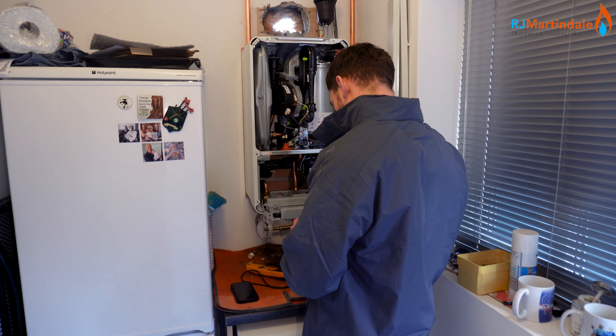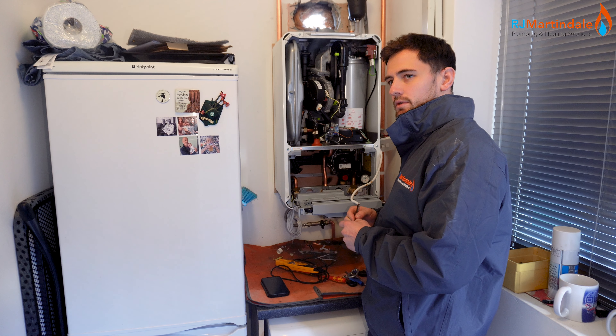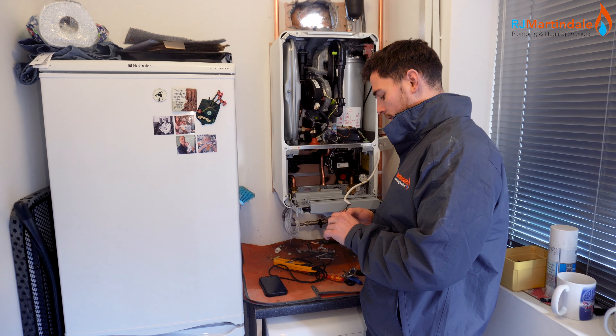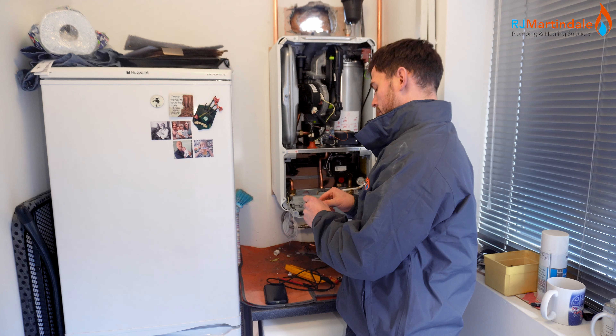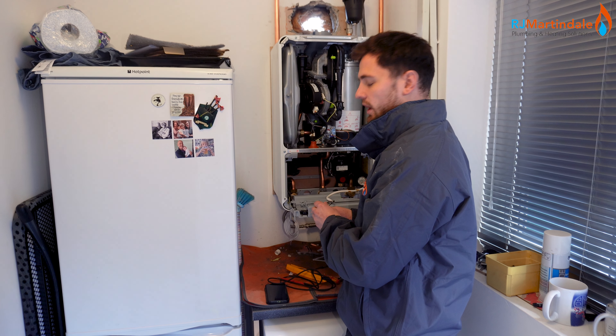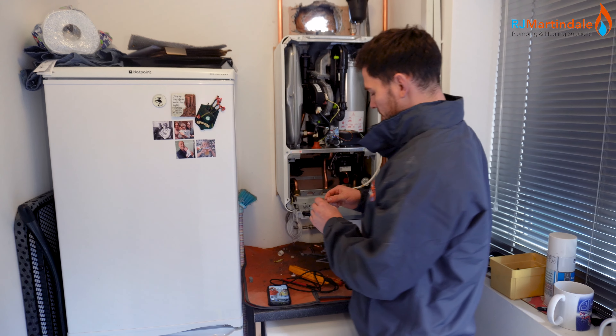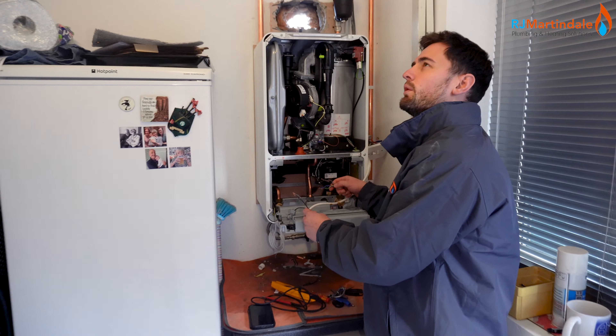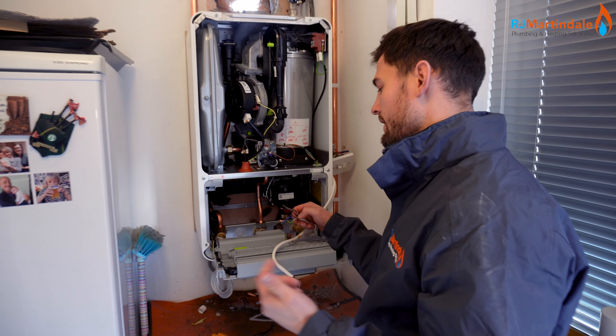Have you got a Fluke on you? Yeah, okay. So what will you do first? Test continuity across the orange and the white of the motorised valve on the three-port. Continuity though - I'm going to drop one wire out, just bear with me. Still got it. So one of them is hot water and one of them is heating. This is one of the old Glowworm, British Gas Glowworm with the built-in programmer that you can control heating and hot water through.